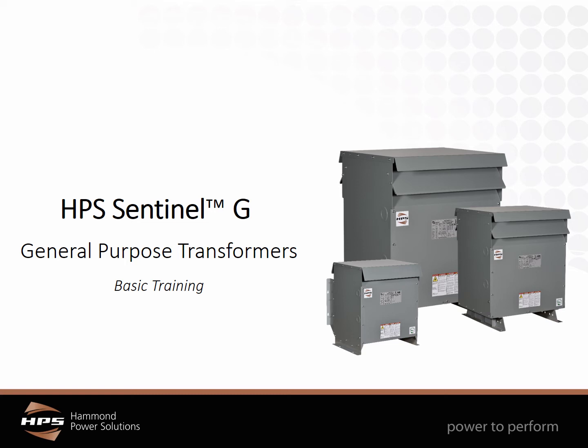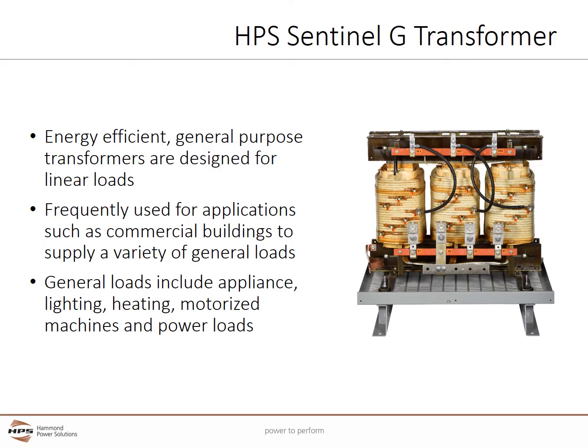Welcome to the HPS Sentinel-G General Purpose Distribution Transformer Basic Training. Energy-efficient general-purpose transformers are designed for linear loads. The most common linear loads are electric heat and across-the-line start motors. Non-linear loads are any time AC is rectified to DC power, in which case K-rated transformers should be considered. General-purpose transformers are frequently used for applications such as commercial buildings to supply a variety of general loads.